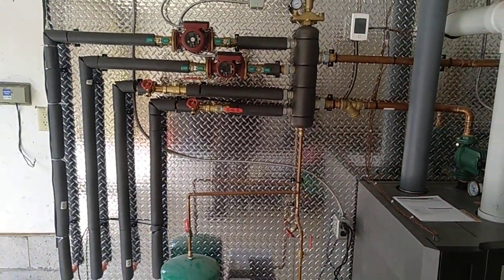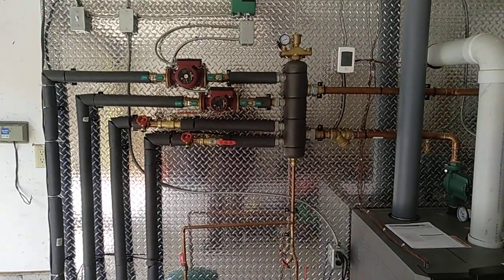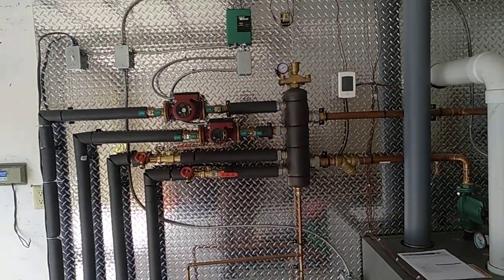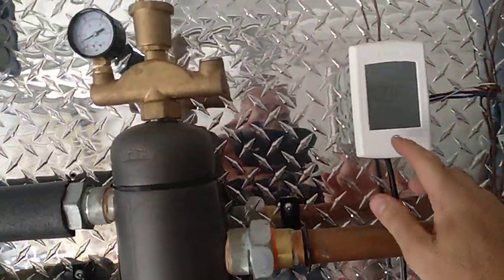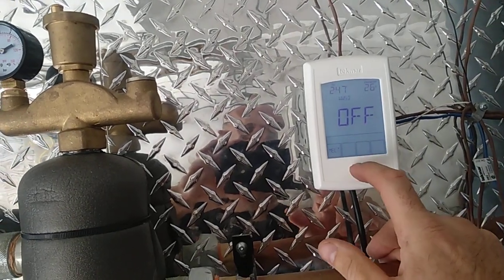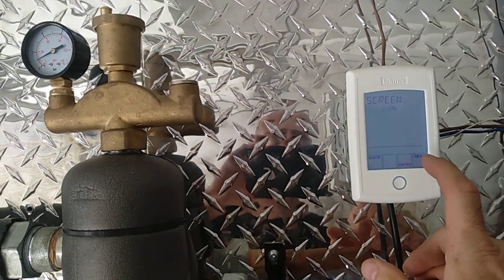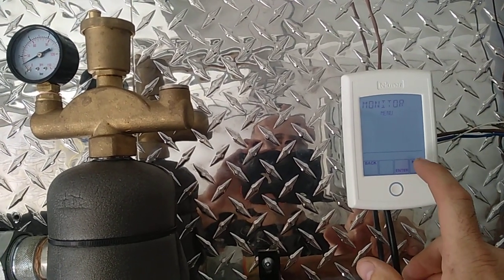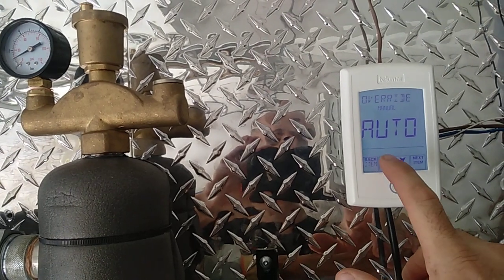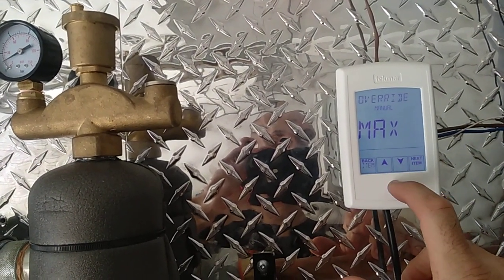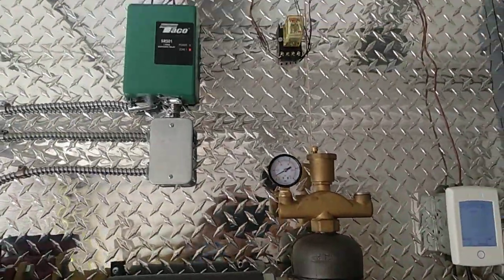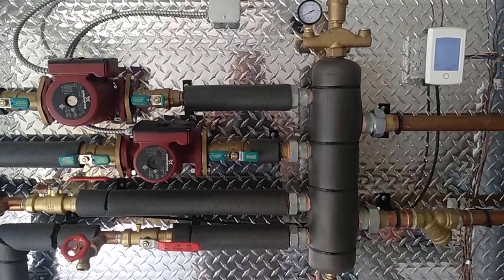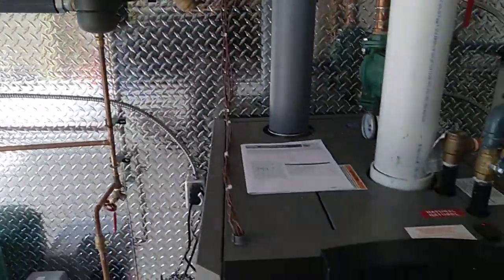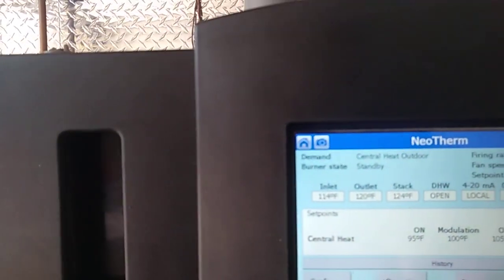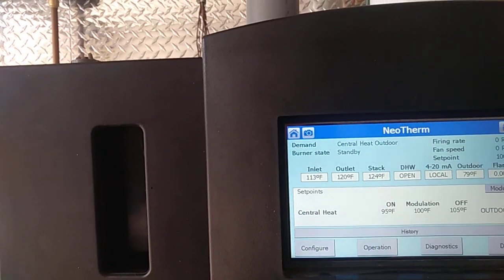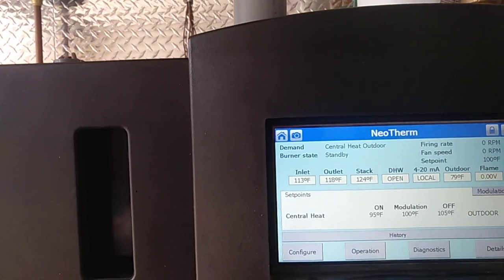We obviously cannot test this system right now to its full potential because it's 30 degrees Celsius. But this nice Tecmar controller has a function that is called override, and that's what we're gonna do. We're gonna override the sensor, and the system will start up until I turn it off. If you look at the boiler, it's in standby. The central heat is on, and it will soon purge and fire.